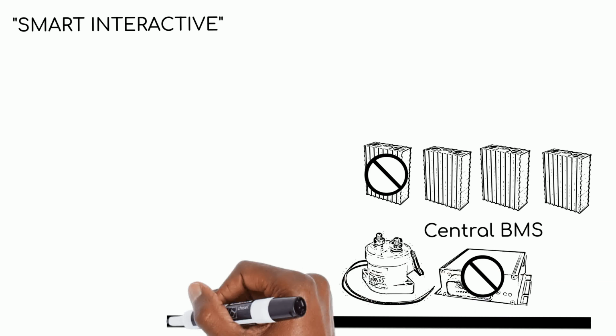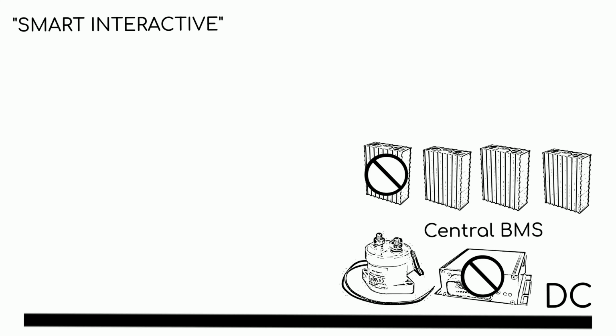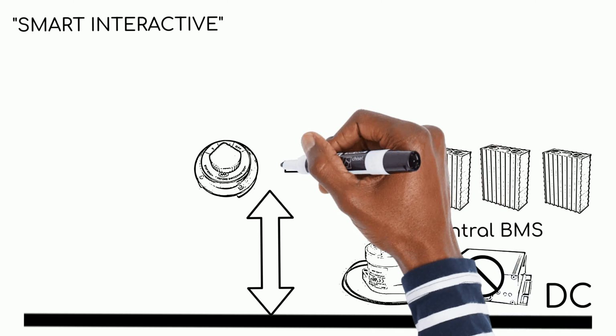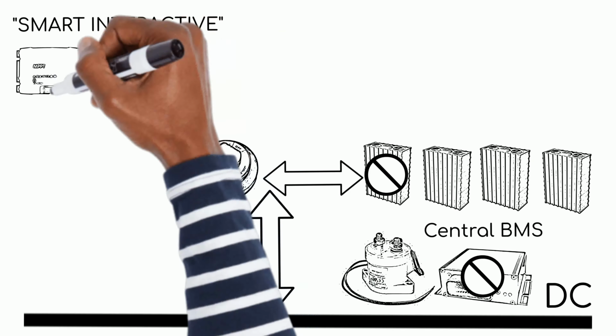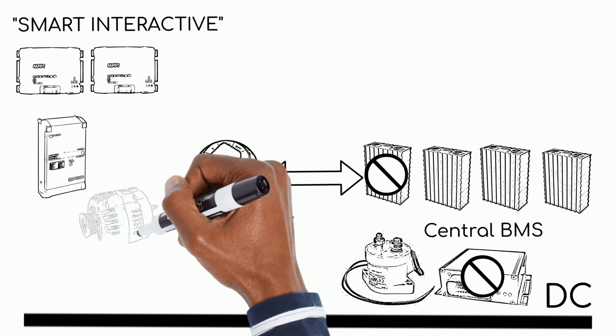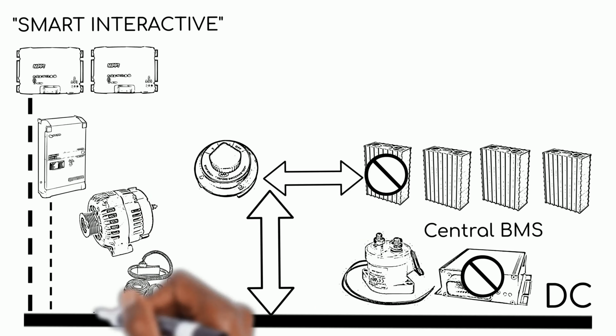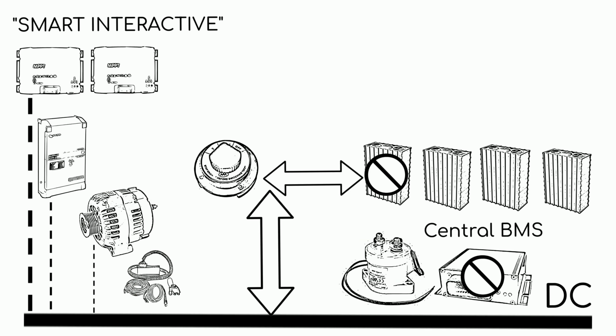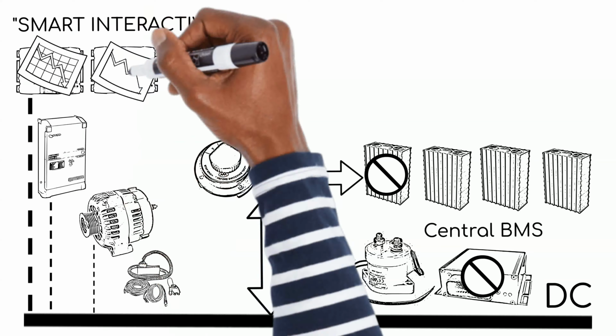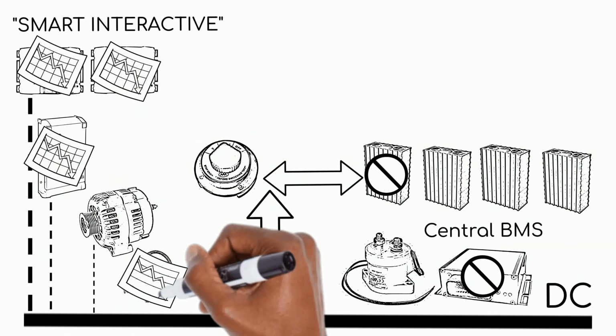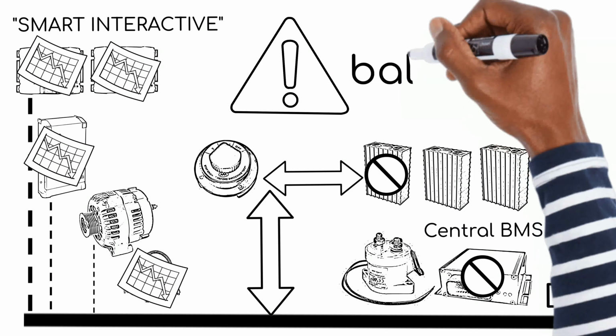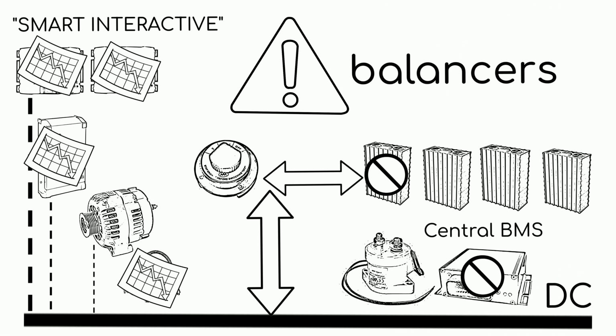In this case, physical actions will be required from the system user. For example, switching to an alternate path, bypassing the BMS contactor relay, if the additional path was created in advance when designing the system. In this case, all chargers can turn on their internal charging algorithms. If the balancing function was part of the central BMS, then balancing will not be available. When using independent balancers, the function will be available.